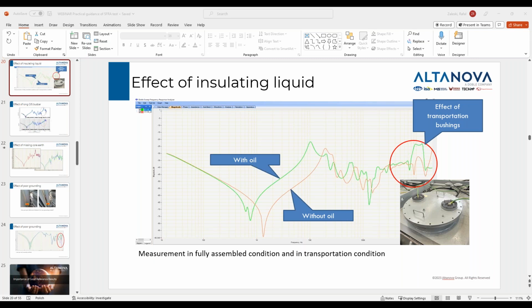Is it recommended to do the SFRA where the transformer, I think, is half full of oil? You saw on the picture before that oil affects the results. If it's half full of oil, it will be a half distorted trace. So it is not recommended to do it this way, but sometimes you have no choice. The transformer is drained of oil for some reason, maybe after some internal review, and you can either test it or not test it. So it's always better to test it in the conditions that you have and then try to interpret it.